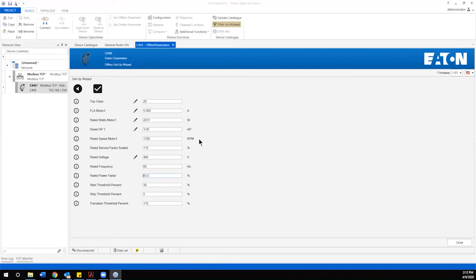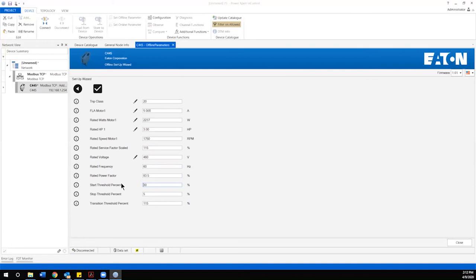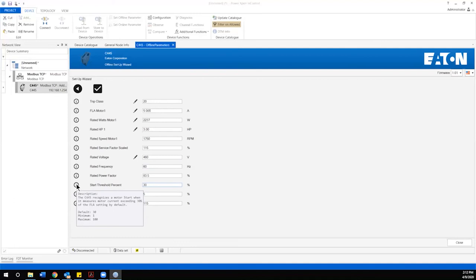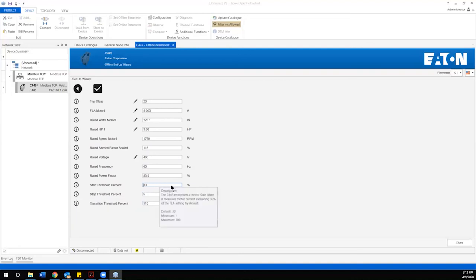The rated power factor should be displayed on your motor nameplate as well and that's commonly anywhere between 80 to 87 percent for most motors. The last three parameters here are subjective. The start threshold percentage is what the system uses to define that it considers the motor to be up and started and it works on a basis of percentage of the rated FLA for that motor. The default of 30 percent is a good place to start with the general application and we'll utilize that.